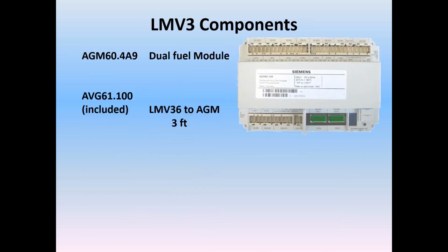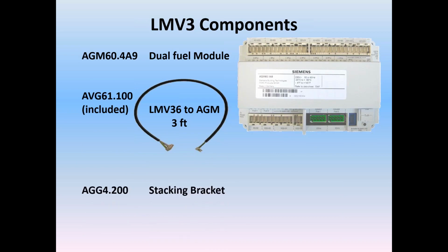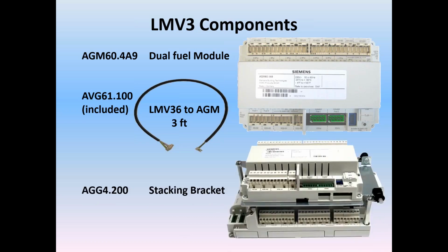The AGM60 dual fuel module has a couple of options. It comes with an LMV36 to AGM cable, and that connects the AGM communication between that module and the LMV itself. Additionally, at SCC, we make a stacking bracket so that you could put the AGM and the LMV side by side, like on the previous slide in your control panel, or to save panel space, you can stack them as the picture shows on the right. It's got a hinged apparatus to it, so you can actually leave it all wired and you can flip it up and put your meters and test points and everything on it in place and cut down on the real estate used in your control panel.